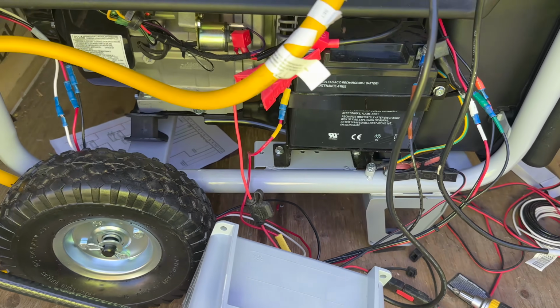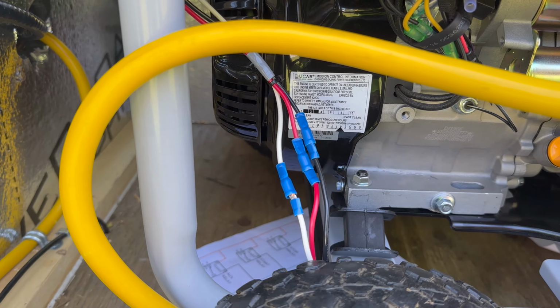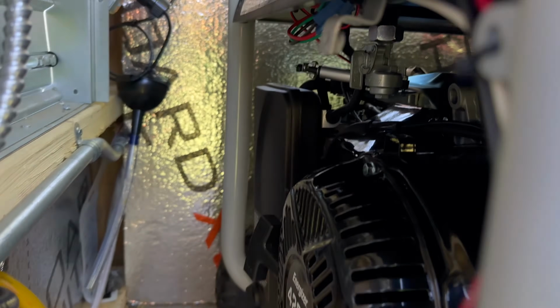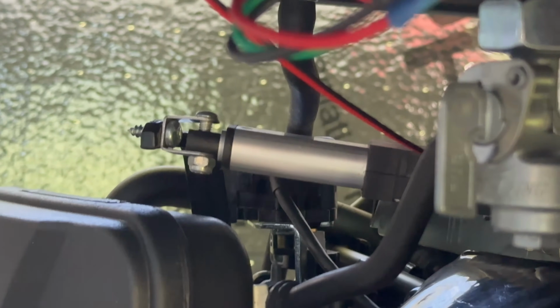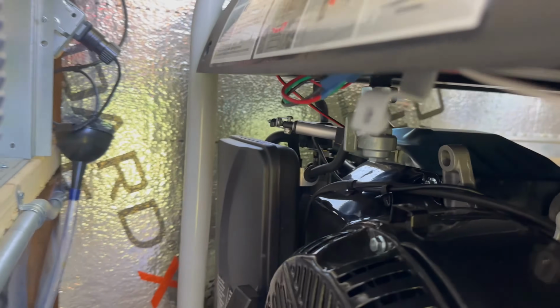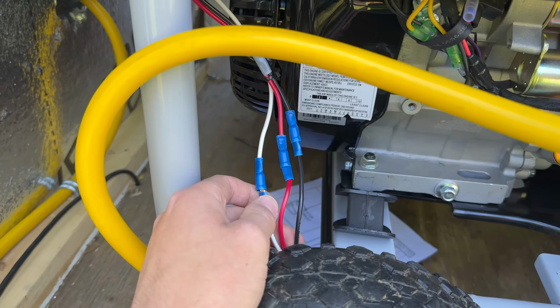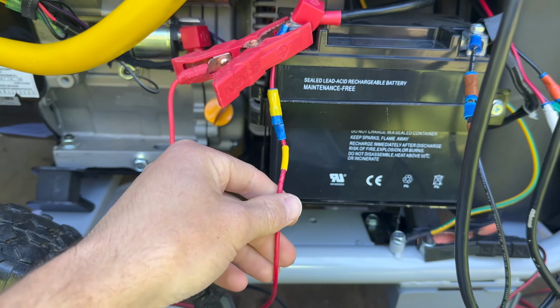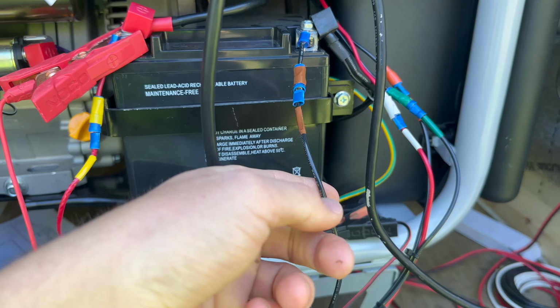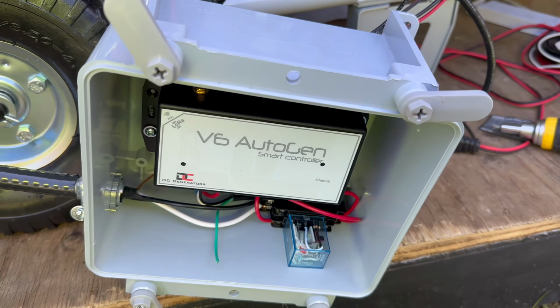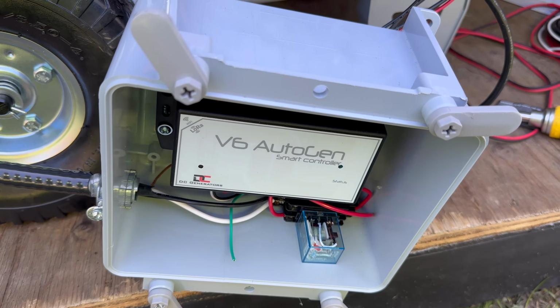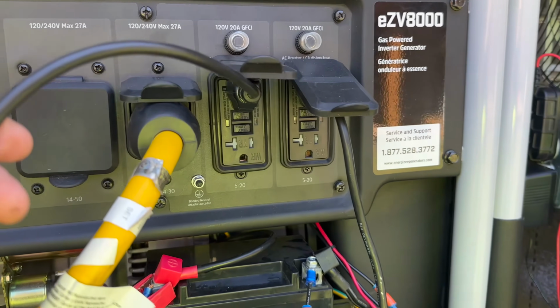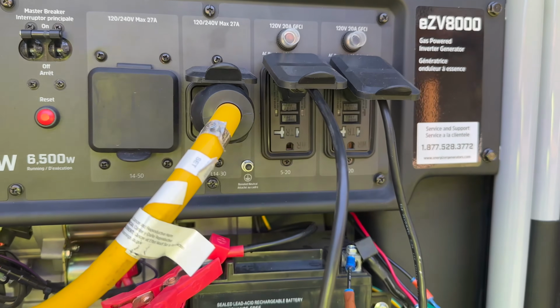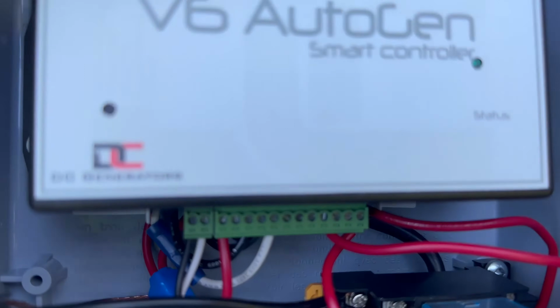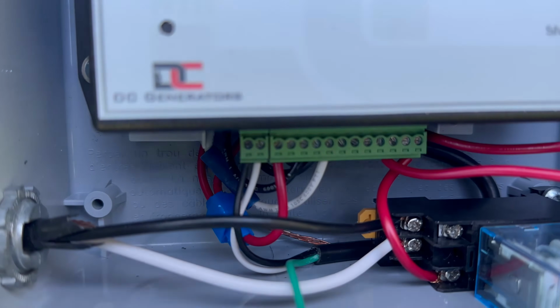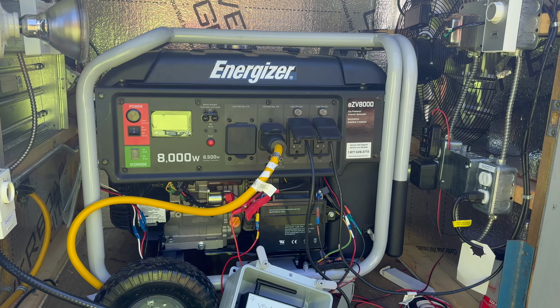However, you can see we have many more connections than just that. We have three connections over here that run to a linear actuator, a very small linear actuator. That is installed on the choke to start the engine. That's the three wires over there, and then we just have a positive connection to the battery and a negative connection to the battery, which power this device. But how does this device actually know once the generator is running? That is done with this cord that is plugged into one of the output receptacles on the generator and tied on to the far left two terminals right there, which is pretty much the entire connections to the generator.